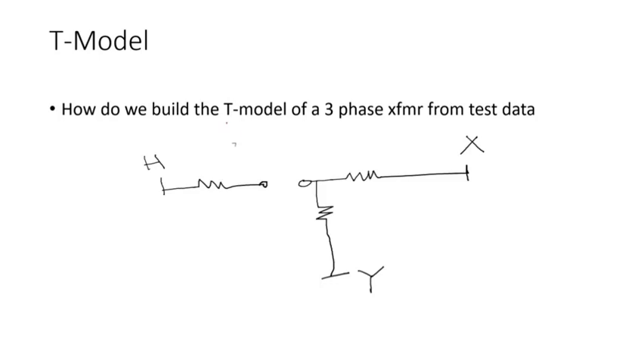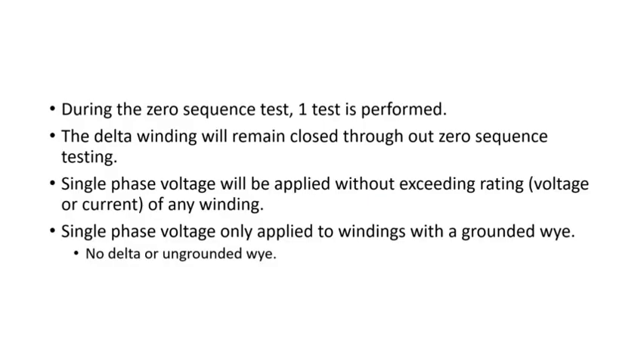In the T-model, the Y side is connected to neutral or ground. The high side, since it has no neutral, has no access to ground — that's why we show it as open. During the zero sequence test, only one test is performed because you have one grounded Y. The delta winding will remain closed throughout the zero sequence test.